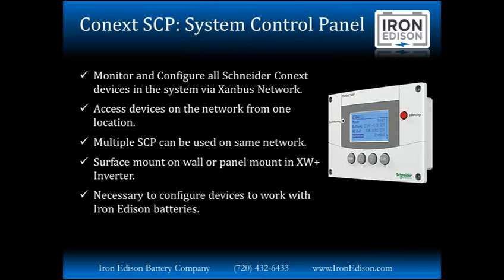Next, we're going to get into some of the accessories available in the Schneider Conext line. First is the system control panel. This is a very critical accessory. It is basically the central control point for the entire system. Using the Xanbus network, the SCP will monitor and also allow you to configure every device on the ZAMBus network, all the inverters, as well as all the charge controllers and other accessories that we're going to get into here in a moment.